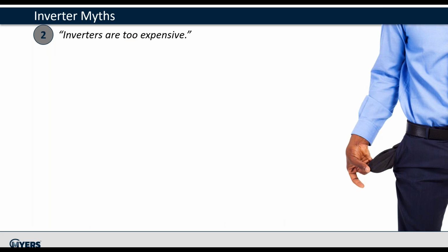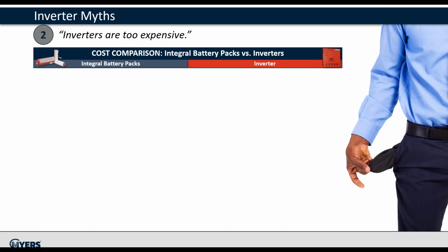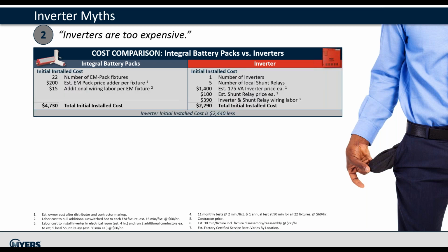Inverters are too expensive. In performing a cost analysis, all aspects within the life of the system must be taken into consideration. For many years, our message was always that inverters may not be the lowest cost up front, but they were the correct choice when analyzing total cost of ownership. With LEDs, that dynamic has changed, and this example will illustrate why.